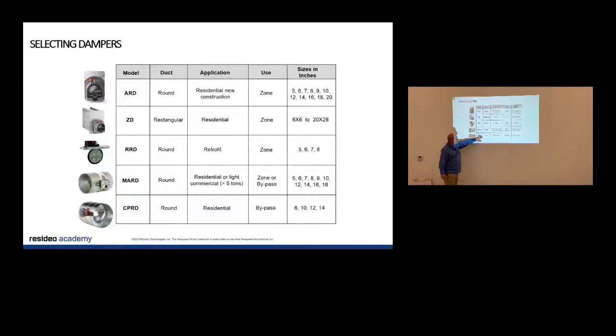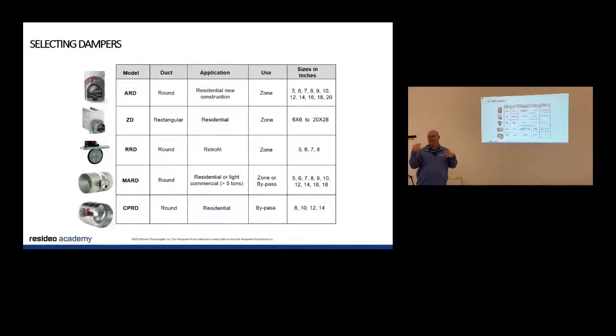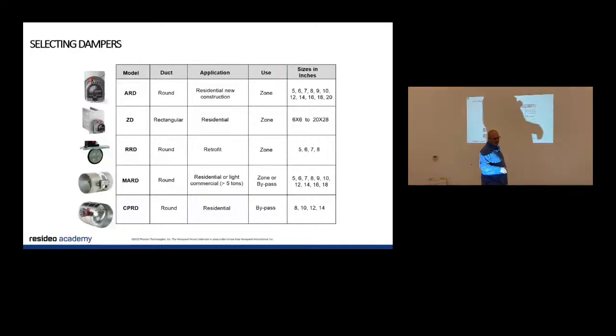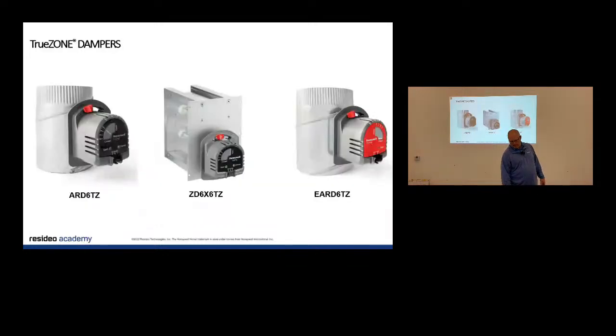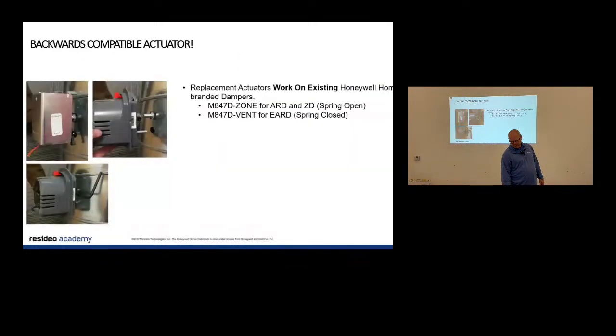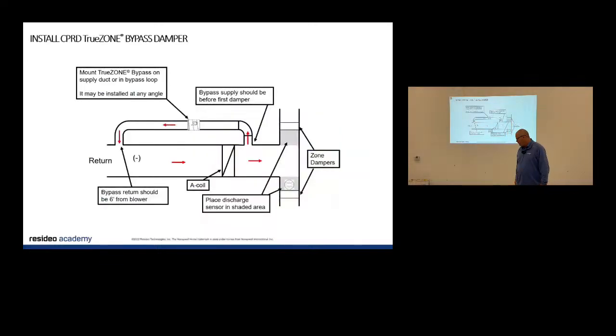And then the bypass is, again, if I've got too many zones, if I've got one smaller area, master bedroom generally, I need to put that air somewhere. So the air is going to go back into the system, and I think that might be the next slide up. Or you can dump it into a non-critical area. Here we go. So the big key with a bypass, let's say I've got one zone out here and it's the master bedroom and I've got too much air. This device is called the bypass. Your air is starting to build up, so it's going to bypass and dump it back in.